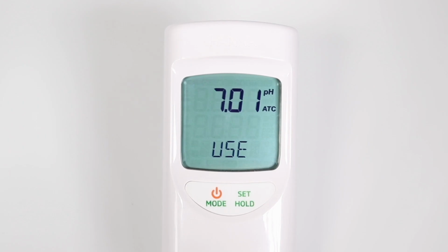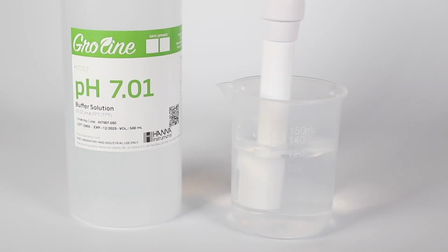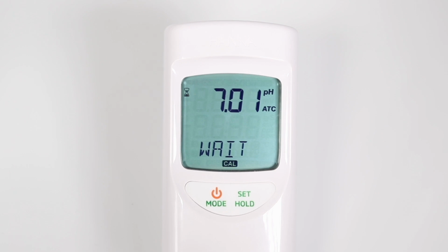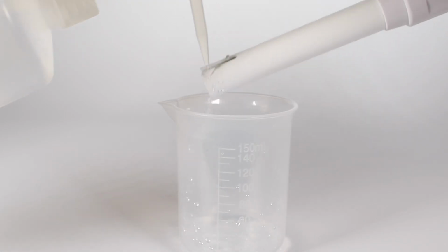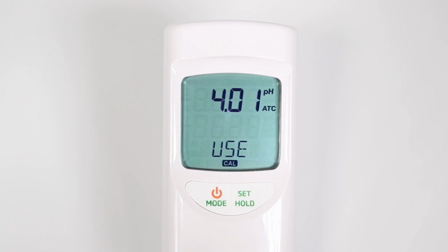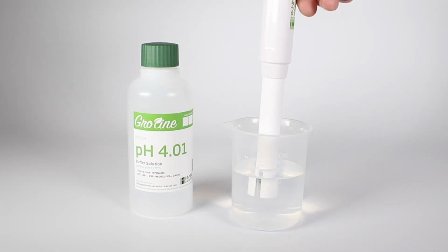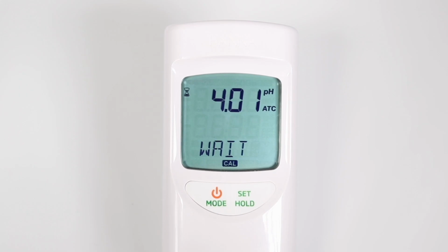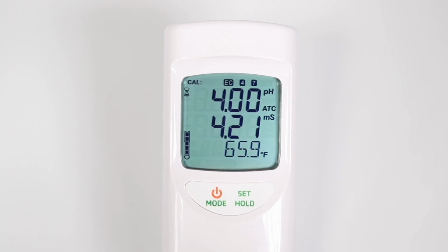If the buffer is recognized, REC is displayed. Then Wait will blink until the calibration is accepted. The pH 4 Use message is then displayed. Rinse the probe briefly and shake off any excess liquid. Place the probe in the 4 calibration buffer. When the second buffer is accepted, the LCD will display Save for 1 second and the meter will return to the normal measurement mode.